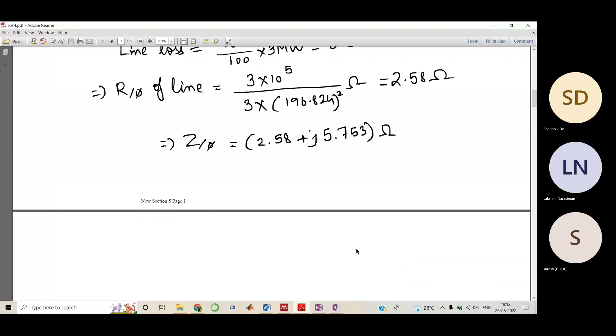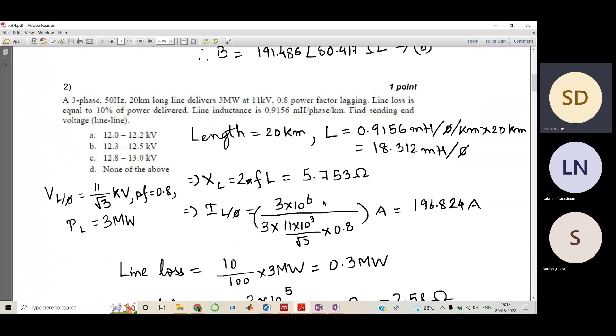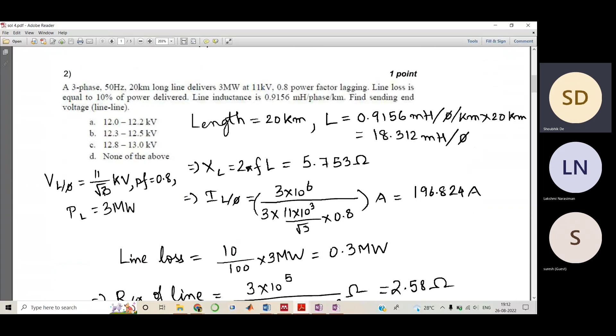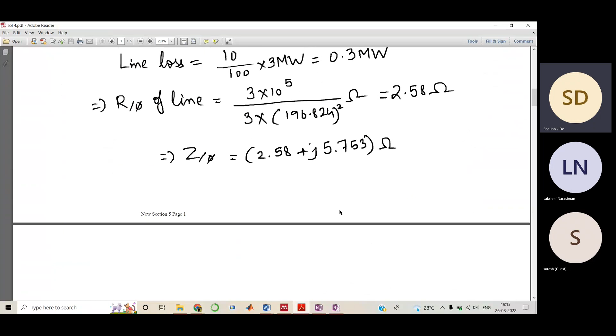Now you can simply calculate the sending end voltage. This is the receiving end voltage per phase, and it is added to the voltage drop across the line. One thing you have to remain careful about is that sometimes we miss this term, 0.8 minus j 0.6. This is the power factor of the receiving end, basically of the current, right? Because the voltage is at an angle of 0, we have to add it to the current only. And it is multiplied with the resistance plus reactance. When you do that, the magnitude comes out to be 7.46.